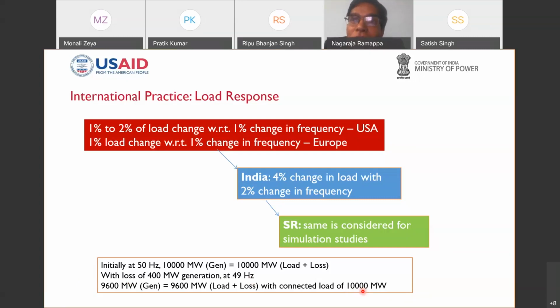Again, as I told you, we should thank our load because the connected load is still 10,000 megawatt, but because the frequency starts coming down, based upon the frequency characteristic, the load is going to come down. Therefore, it becomes, say, 49 Hz, because 2% change in frequency gives 4% change in load. Therefore, at 49 Hz, there is again a load and generation balance.